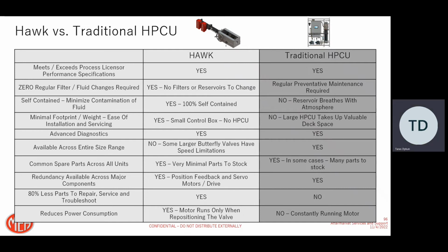Available across the entire size range? Unfortunately, Hawk isn't. For some very large valves, especially expander inlet control valves, there is a speed limitation for Hawk. Even for some HPCU units, it makes it very difficult to operate the valve within 1 second modulation speed. As a result, there is a limitation. For HPCUs, there is no limitation. Common spare parts across all the units, yes. Hawk has very minimal parts to stock compared to HPCUs. Redundancy available across all components, yes for Hawk and yes for HPCU type systems.